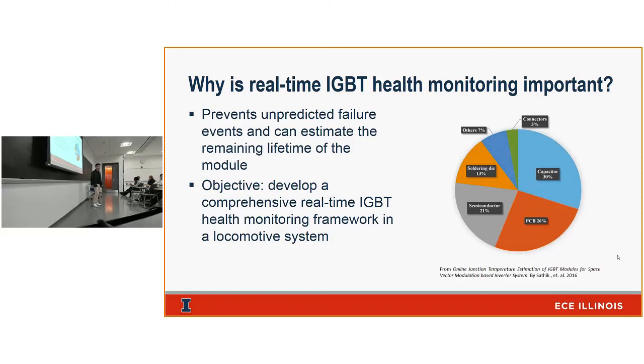One other thing we're doing as part of this project is developing a fault identification board. In case of a fault—say when the DC link voltage exceeds a certain limit, or when current through one of these IGBTs exceeds a certain limit—this data storage board will store all the measurement data so it can be analyzed later. This board needs to be separated far away from the IGBT power module in case of failure.